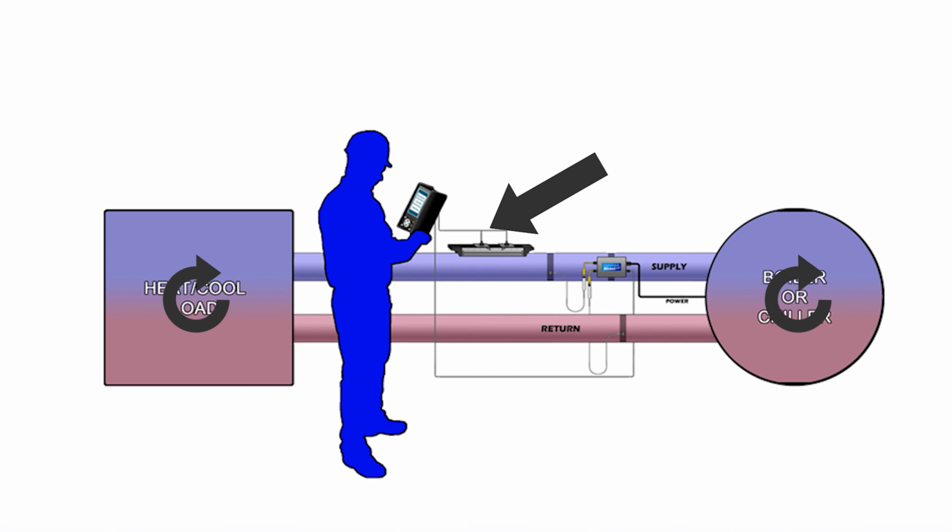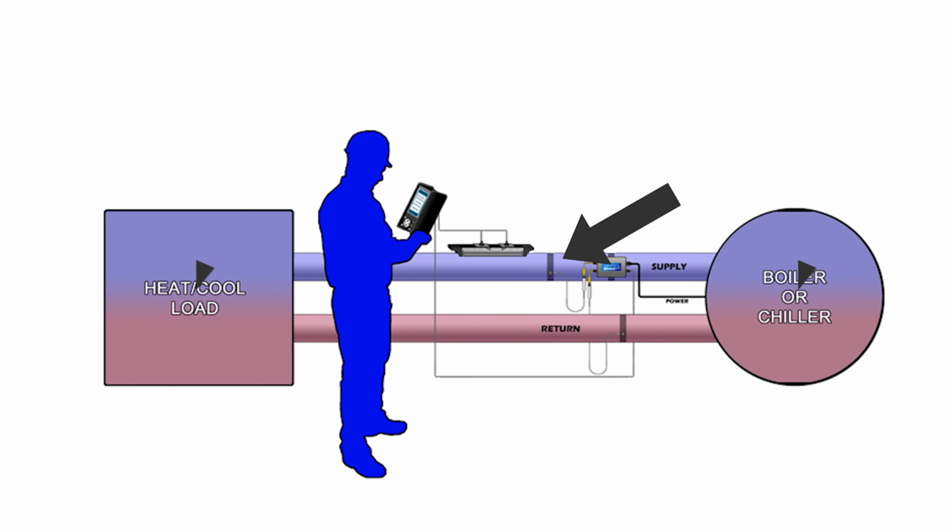Now to measure temperature, we need to use precision RTDs calibrated as a pair and strap them on the supply and the return lines in the same position, typically 3 o'clock. Now the outside of the pipe temperature is not the same as the inside processed liquid. However, remember, the quest is to come up with a temperature differential, not an exact processed liquid temperature.